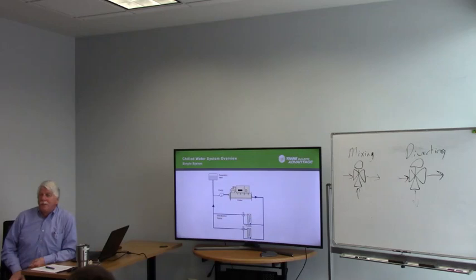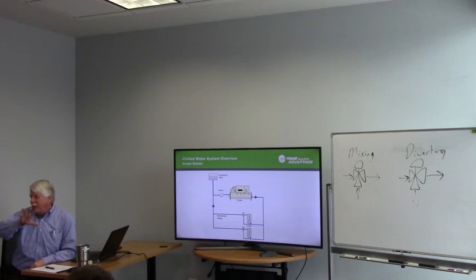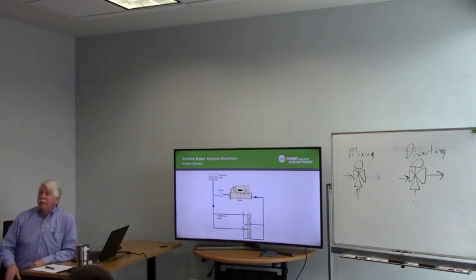So I'm operating a rooftop unit at 10,000 CFM, everything's at steady state. Somebody says, I want 11,000 CFM. Well, whatever static that thing was operating at before, it's going to have to be 120% of that static to deliver that air. That's the square relationship between static pressure and RPM.